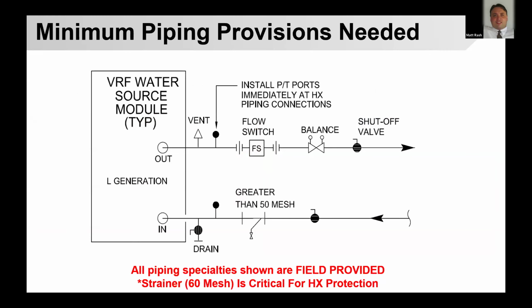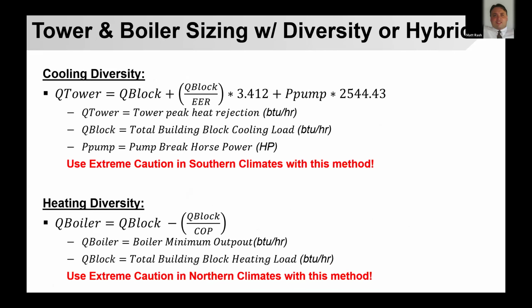There are some minimum piping provisions you want to be careful of and mindful of with this product. As I mentioned, it's brazed plate technology, so it can be prone to clogging if the loop isn't properly maintained and flushed. We do recommend a 60 mesh strainer on these brazed plate heat exchangers, and then obviously some means of balance and flow switches. And there are other things that can be done to accommodate variable speed hydronic pumping on the condenser water side. That's outside the scope of this presentation, but we have information on that available.